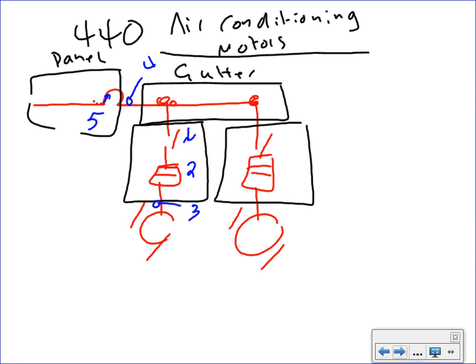What are we going to size? Not sizing the controller. If you were to size a controller, guys, it's very similar to motors. Controllers and overload are very similar to motors. Controllers and overload come sized with this HVAC equipment. That's why they're not a big deal, but they're almost identical to motors. I'm just interested for this equipment in a disconnect, overcurrent protection device, branch circuit, feeder conductor, and feeder overcurrent protection device.